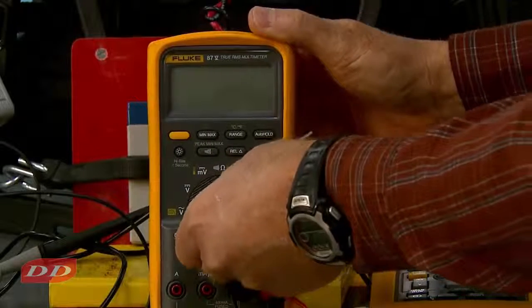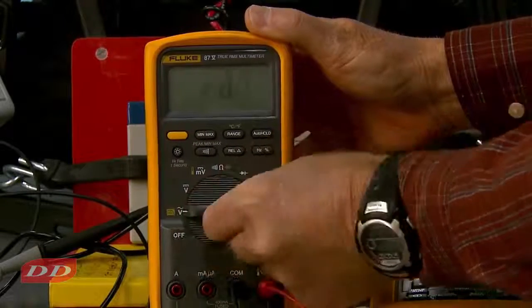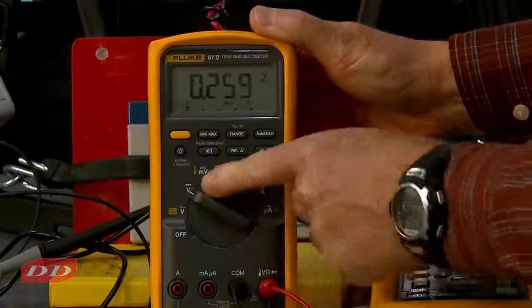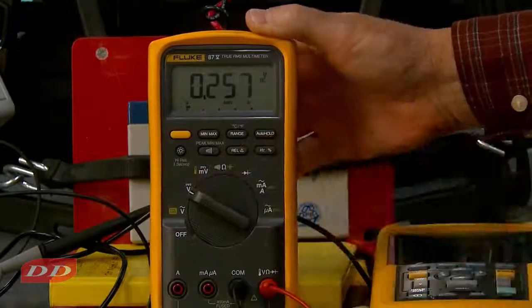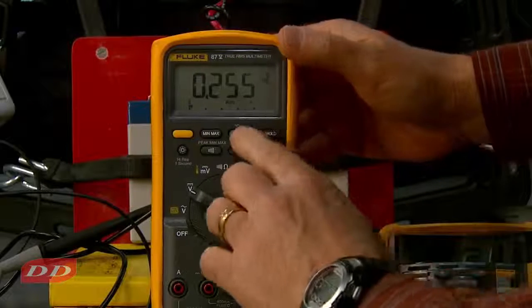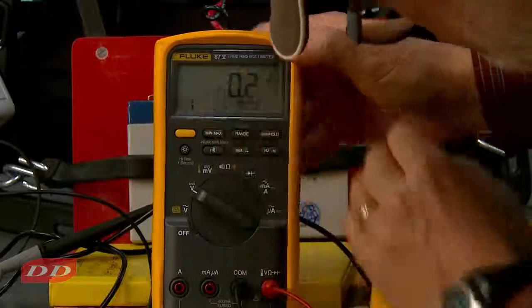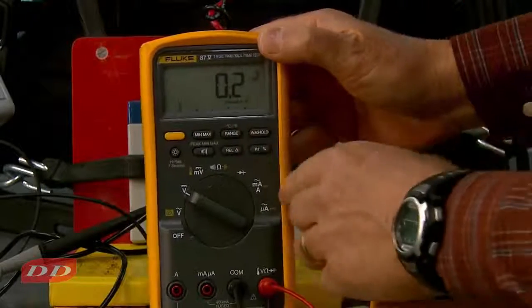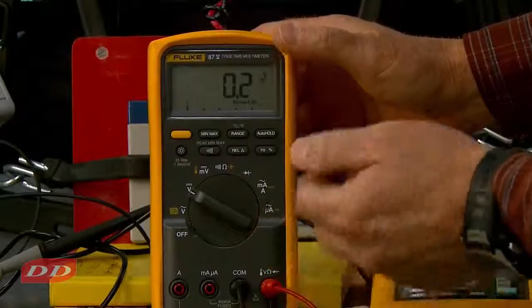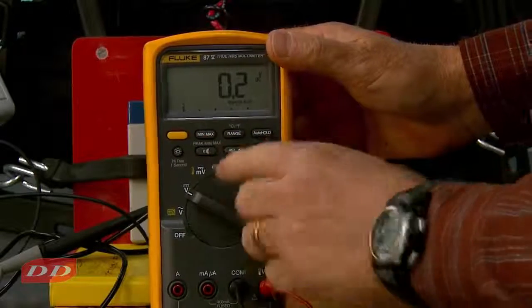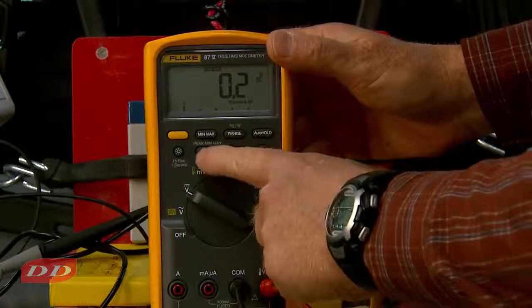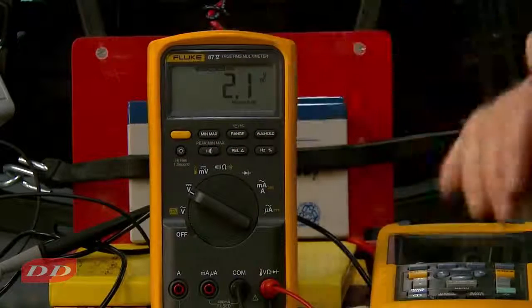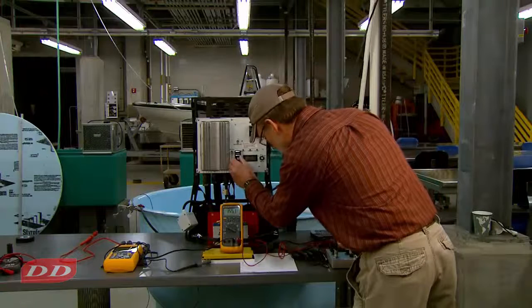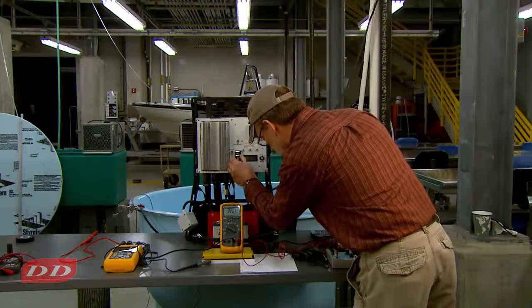And now we're going to turn the multimeter on so it'll measure peak voltage. We need to turn it to DC volts, because we're doing pulse direct current. We want to set the range to where it'll take in the voltage that we're dealing with, hitting the range button, and we want to have it measure peak volts. And on this particular unit, I have to hit a min-max button and this button, and it will then read peak volts. So let's turn the voltage up now to 200.